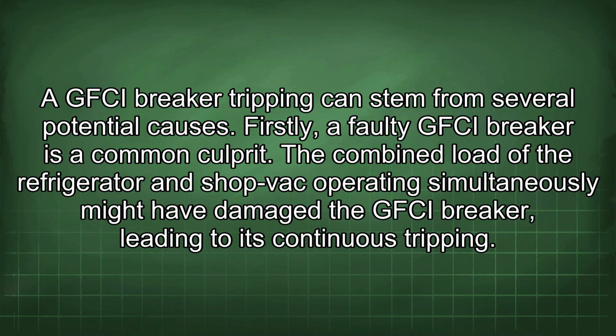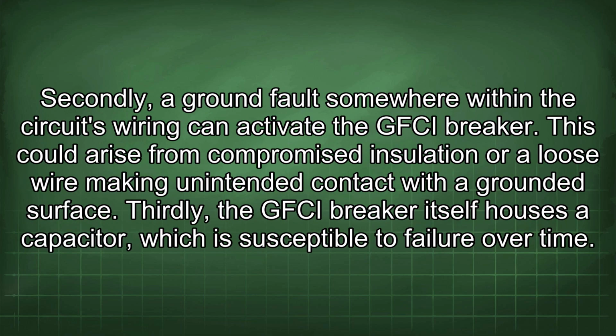A GFCI breaker tripping can stem from several potential causes. Firstly, a faulty GFCI breaker is a common culprit. The combined load of the refrigerator and shop vac operating simultaneously might have damaged the GFCI breaker, leading to its continuous tripping. Secondly, a ground fault somewhere within the circuit's wiring can activate the GFCI breaker.